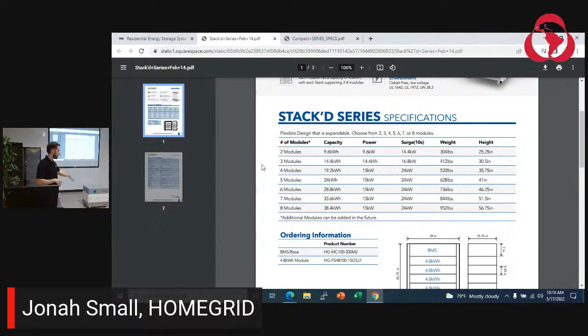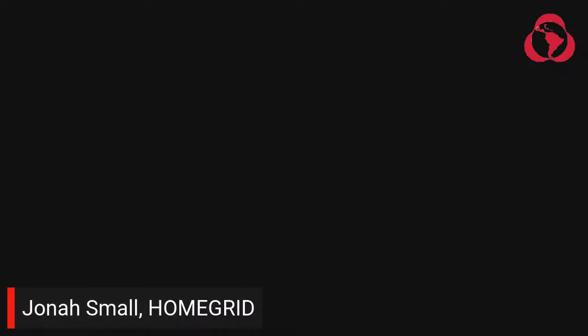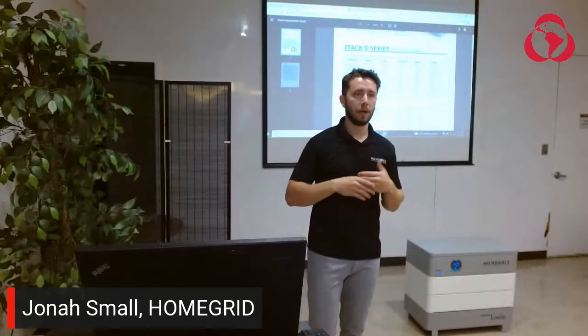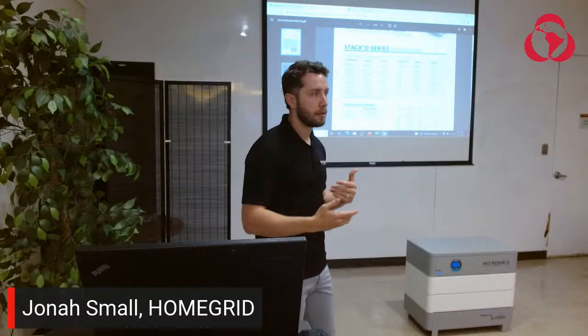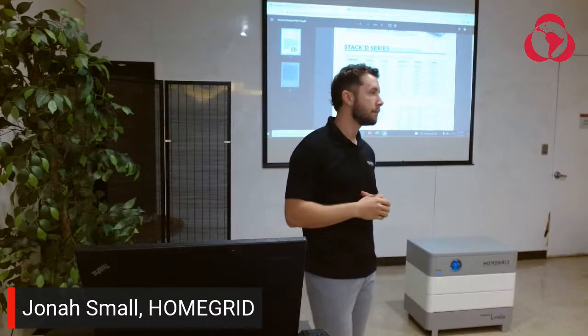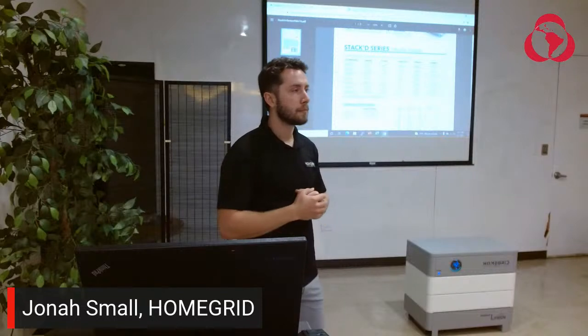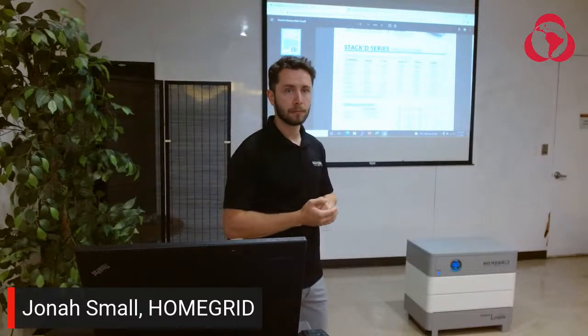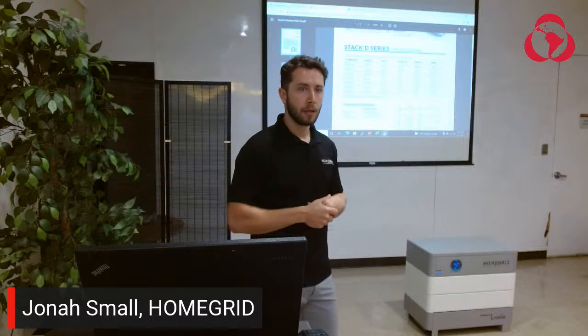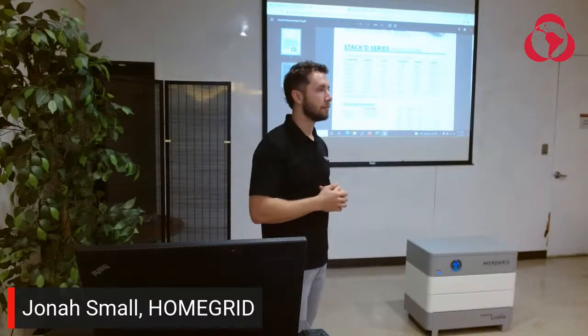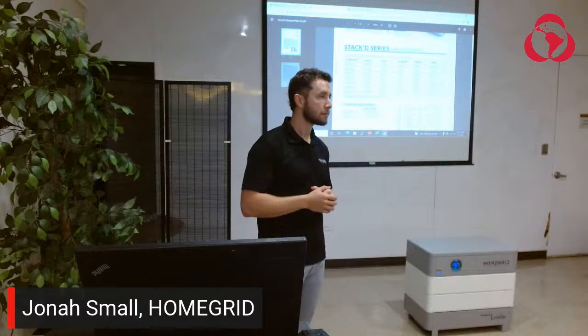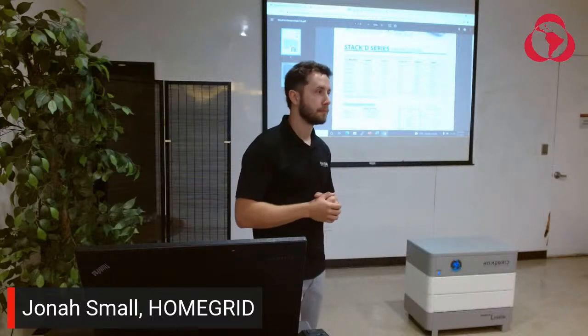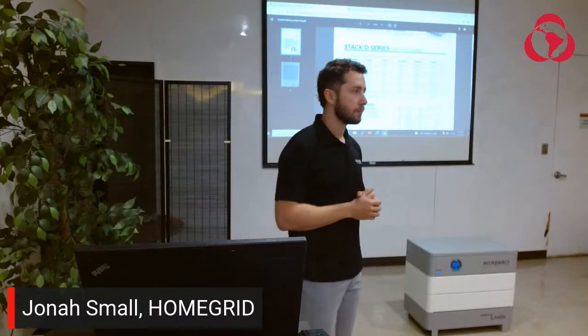So the way that we have the safety protocols in this battery is we have a main BMS, a main controller here, but each of the modules also has its own controller at the cellular level. So for upgrading the capacity later, there's no safety concern. Other brands only give you 1 year to add to the older model. In general, if you're going to install new modules, you need to lower the existing modules to the voltage of the new one so they can match. Here you can have a depleted module and install a new one, and they will work separately.